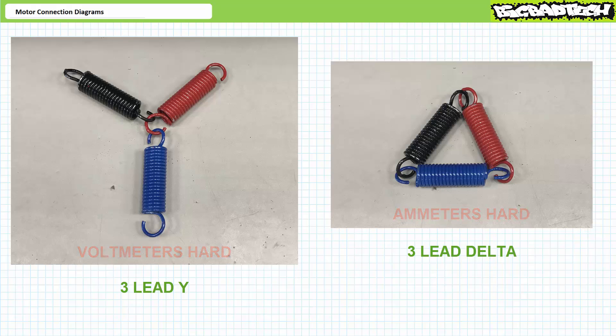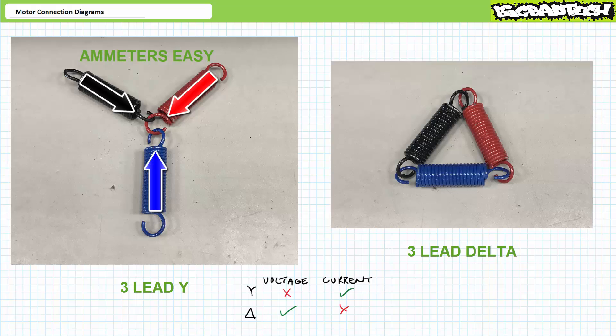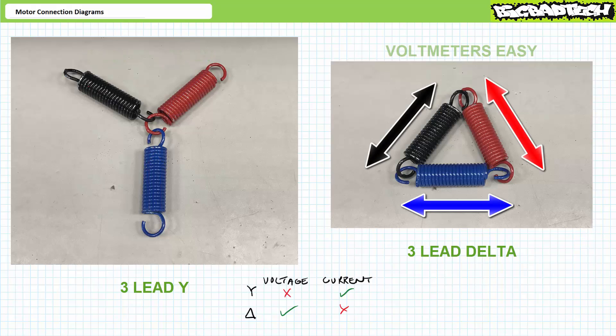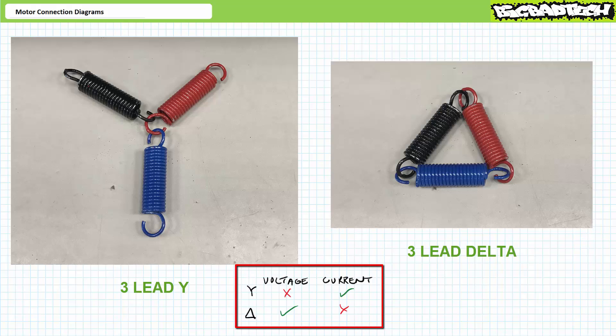Some properties are easier to obtain depending upon configuration. Measuring current through an individual winding in a Y-configured motor is easy — an ammeter can always be inserted in series between the source and the external lead of the winding of interest. Similarly, measuring voltage across an individual winding in a delta-configured motor is easy; a voltmeter is placed across the two external leads of the winding of interest. In summary: it's easy to measure current through a Y-configured winding but hard to measure voltage across it, whereas the opposite is true for delta-configured motors.